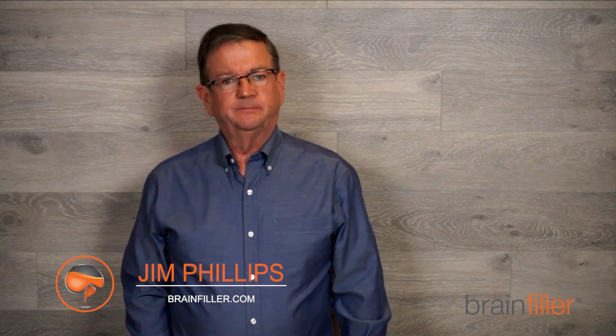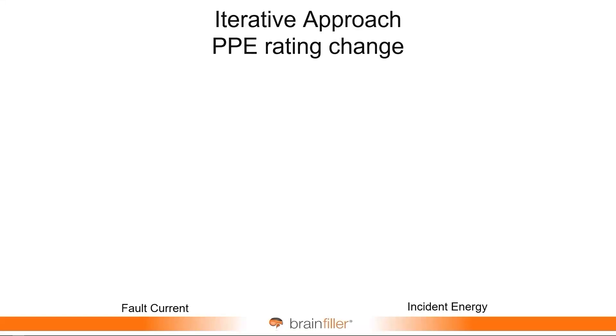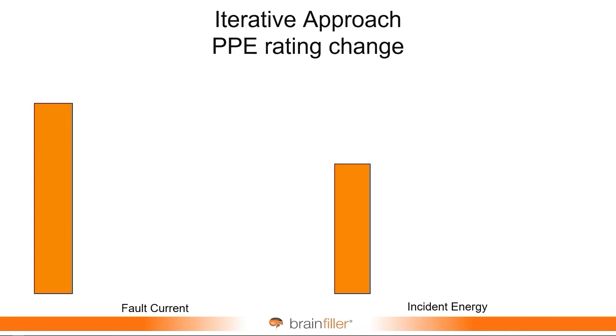Sometimes people will question — well, I don't actually know the actual fault current from the utility, or it could vary or something like that. So for years now, I've been advocating in that case — it's not a perfect answer — but perhaps use an iterative kind of approach. What that is: you begin with the initial fault current, basically the highest fault current, and you conduct your study, and you'll get a resulting incident energy.